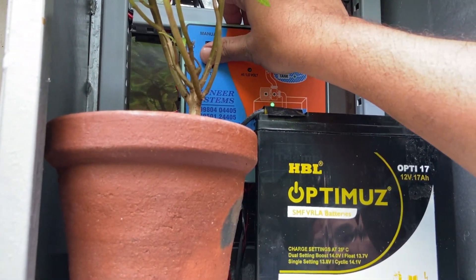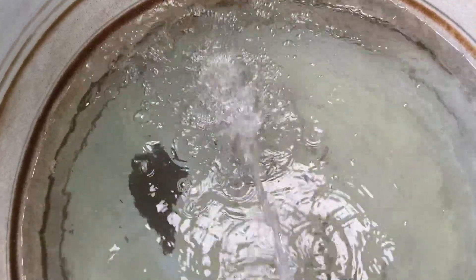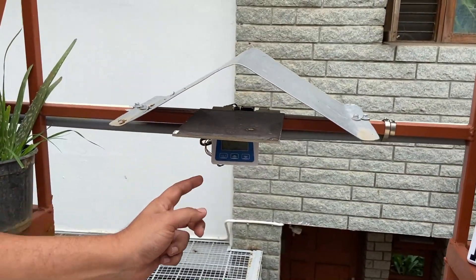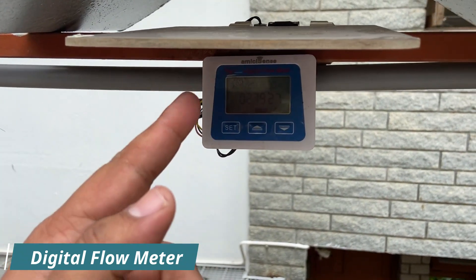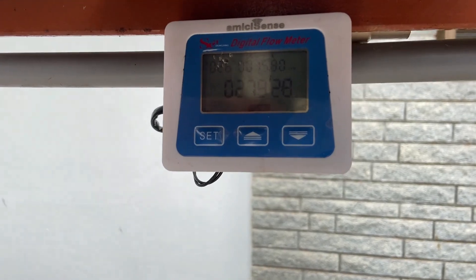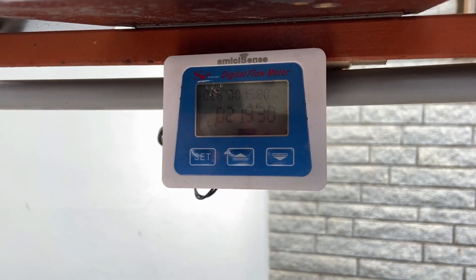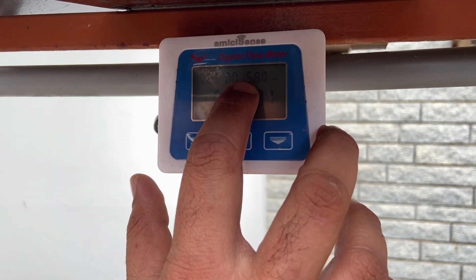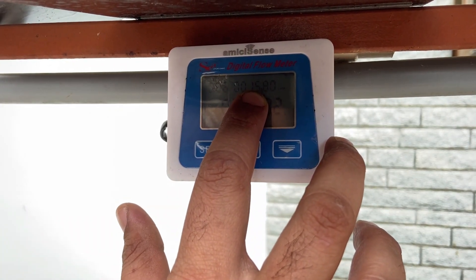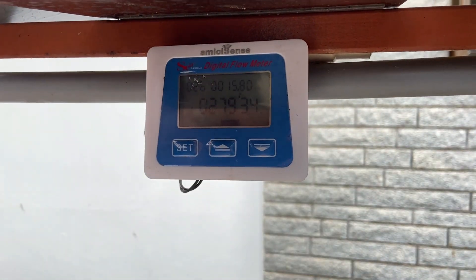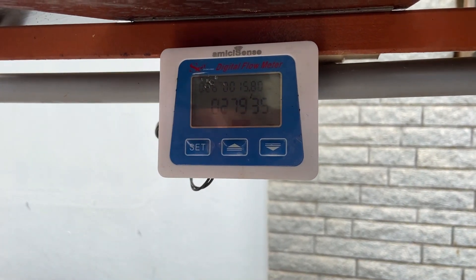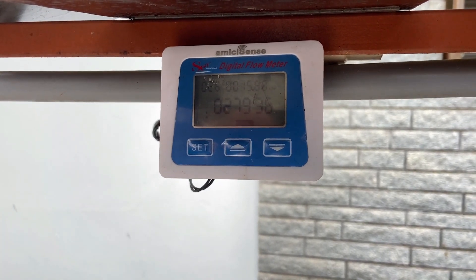Since the tank is already full the pump is not running automatically, so for the purpose of this video I will switch it on manually. The water is now being pumped, flowing through this pipe. We have a digital flow meter here for measurement. In our calculation we need to pump at 13.3 liters per minute — the flow meter is now showing 15.8, 15.7, 15.9 liters per minute. So if we pump at this rate for about two hours we will fill the tank to 1600 liters.